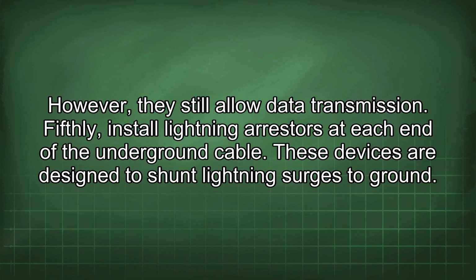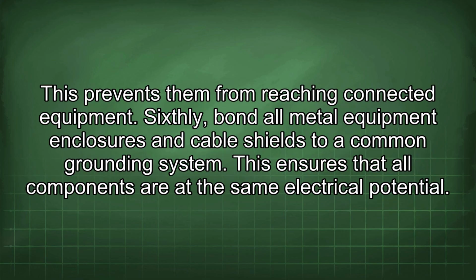Fifthly, install lightning arresters at each end of the underground cable. These devices are designed to shunt lightning surges to ground. This prevents them from reaching connected equipment.